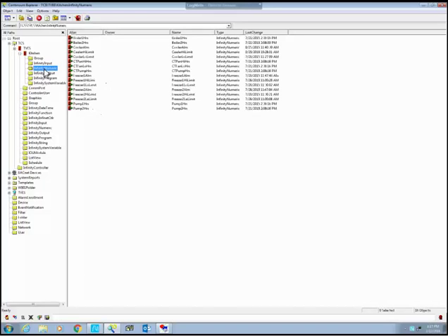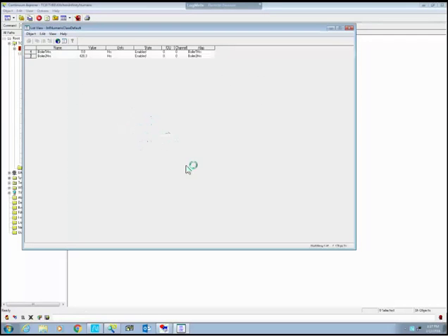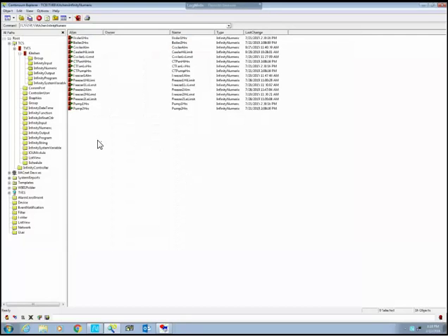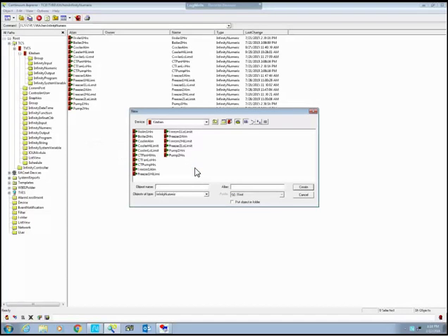We go to the Numerics tab. Here's what is existing. If you do a view, it's just going to give you the values. There's no channels associated with the numerics because they're not physical points. If I want to create one that is, we'll say a set point. I want a new infinity numeric.